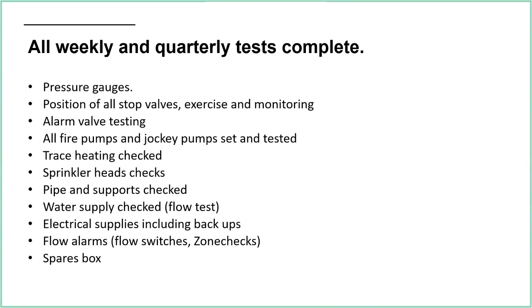Electrical supplies, including backups, checking all those. All the flow alarms, so generally that's flow switches, and generally that's zone checks. That's going to save you a lot of time on commissioning, because they can just turn a key or press a button to test those systems rather than draining water. Spares box, finally. So just checking that there is a spares box and it is fully stocked, which obviously it should be at the start of the job.